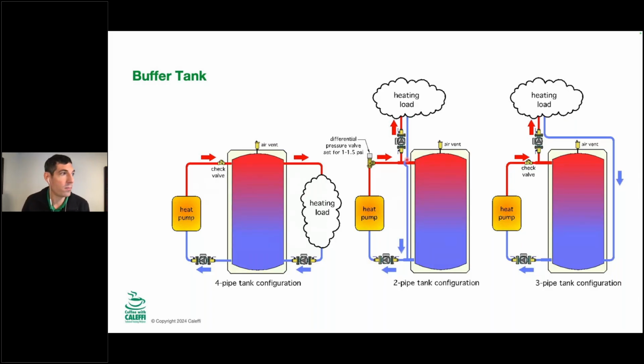This is a system that I know my dad had running in the shop that he had in Missouri for a long time. So this will work. This goes direct load, which is an advantage. This 3-pipe is similar, but on the way back, the water is coming back through the bottom of the buffer tank. So you're always charging that buffer tank on the way back. So if you turn on this heat pump, it's not going to turn off until you get your tank sensor up to whatever you wanted, if that's the way that you set it up. So you're always going to ensure that you charge the buffer tank at the end of the cycle.